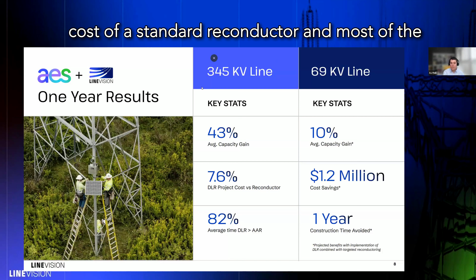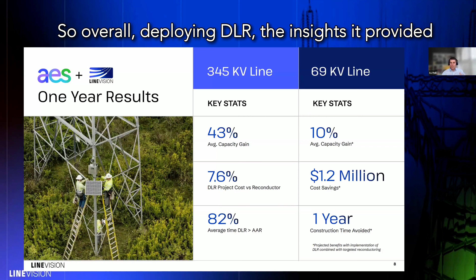Most of the time, the DLR rating is even above ambient-adjusted ratings—we'll get into more detail there. On our 69 kV line, we identified the ability to increase capacity through a targeted reconductoring solution that can achieve $1.2 million in cost savings and avoid a year of construction time versus a standard reconductoring process. Overall, the insights from deploying DLR and the additional capacity gains clearly proved out the cost-benefit ratio for us, and we'll get into some other use cases beyond capacity gains.